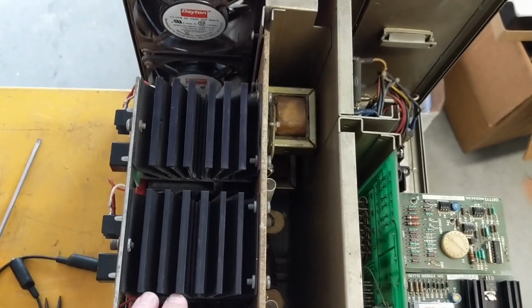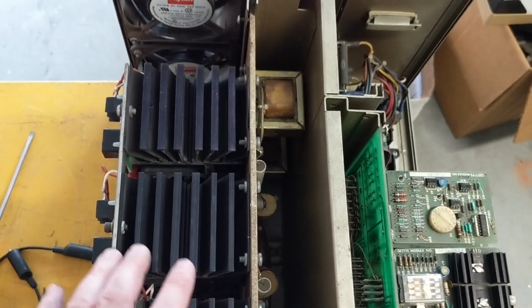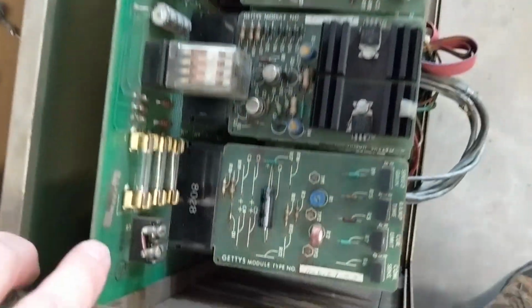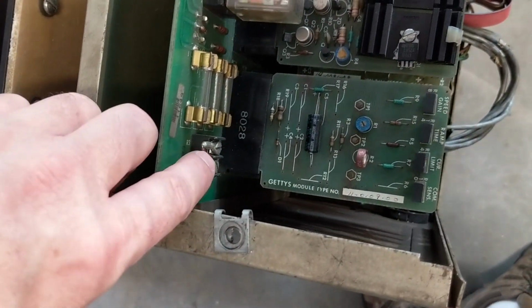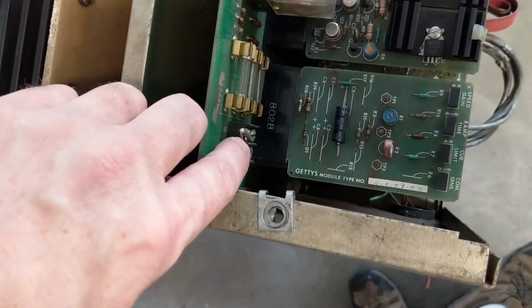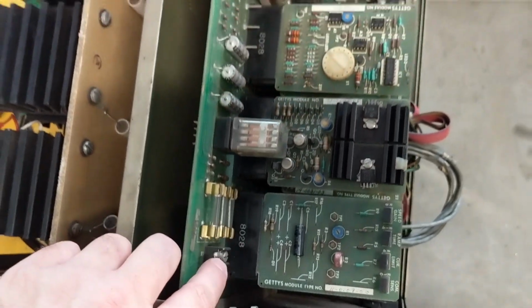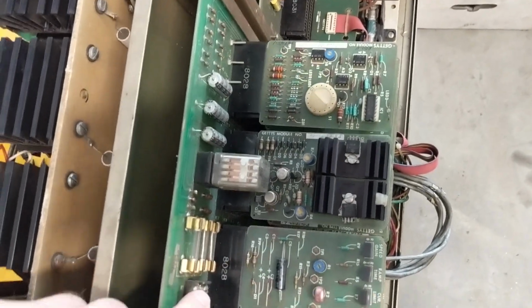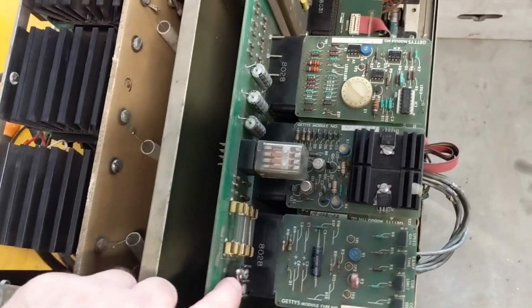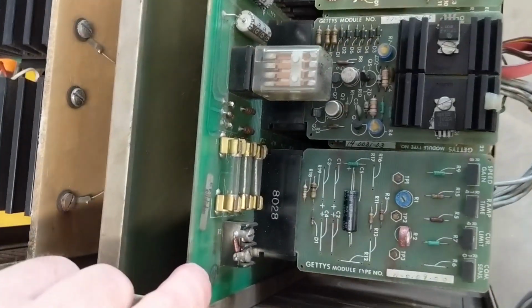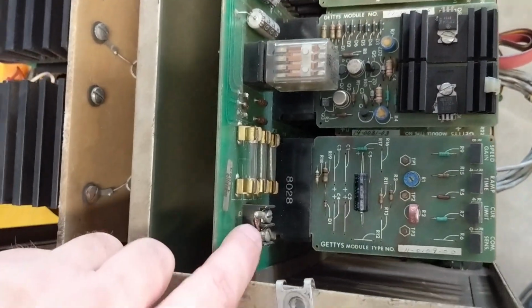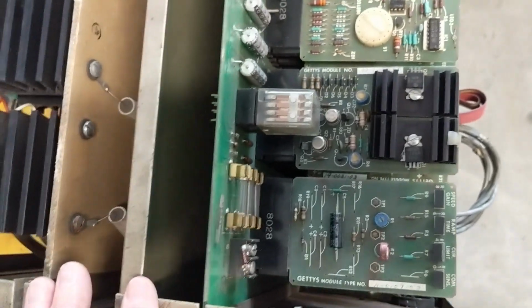They both had this drive. One had a different resistor here for the horsepower. Both drives are actually 20 horsepower, but one had a 10 horsepower resistor, and of course the 20 horsepower having a resistor for the 20 horsepower. So that's the difference. So I also replaced them with a 20 horsepower drive, that way, with the same drive, either motor works.